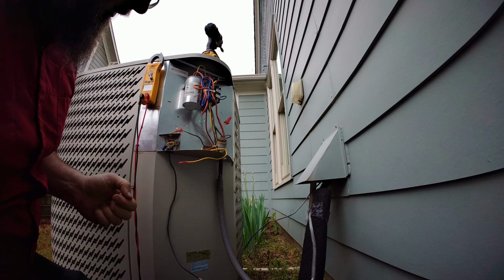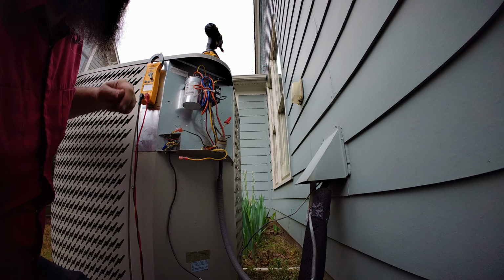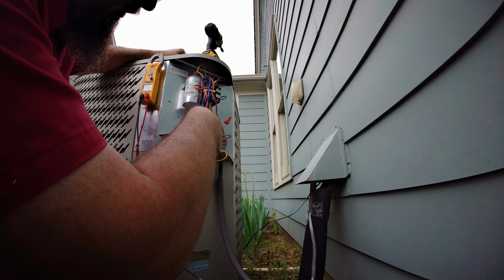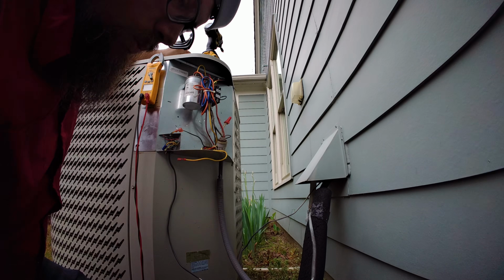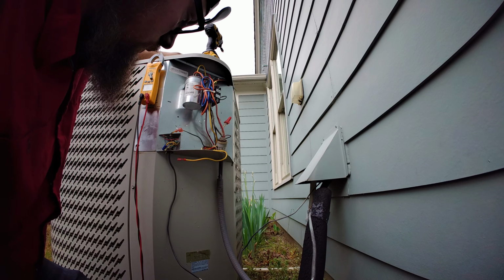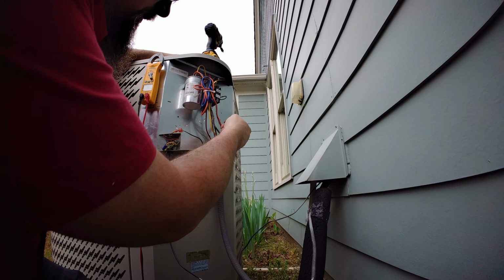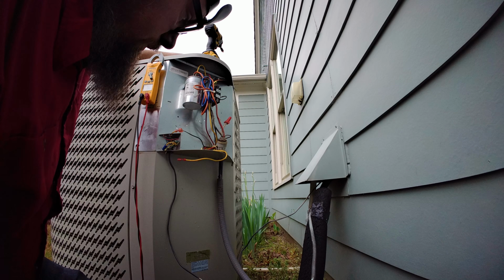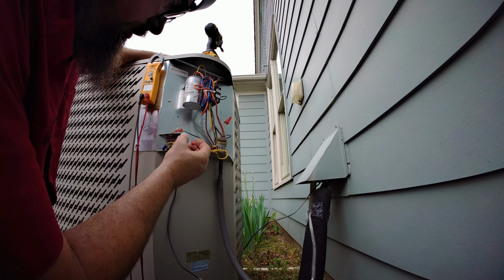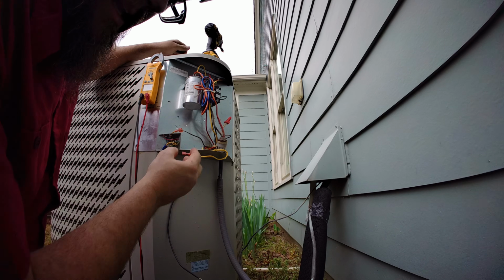And essentially, when I was checking these 2 wires here, this one goes through a pressure switch, comes back, attaches to one side of the contactor's 24 volt coil. This just goes directly to the other side of the 24 volt coil. So electrically speaking, I was just checking the contactor coil through that.